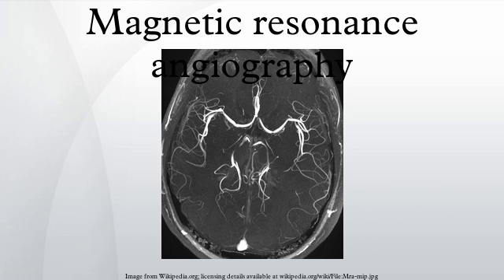Subtractionless contrast enhanced magnetic resonance angiography: recent developments in MRA technology have made it possible to create high quality contrast enhanced MRA images without subtraction of a non-contrast enhanced mask image. This approach has been shown to improve diagnostic quality, because it prevents motion subtraction artifacts as well as an increase of image background noise, both direct results of image subtraction. An important condition for this approach is to have excellent body fat suppression over large image areas, which is possible by using M-Dixon acquisition methods.